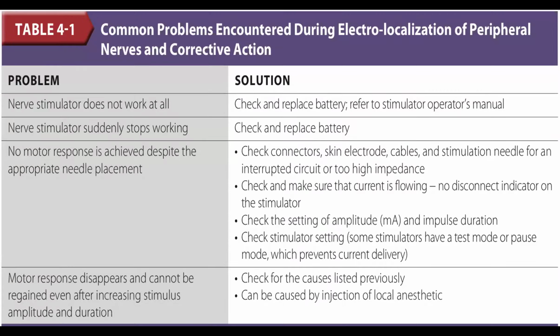And coming to common problems encountered during localization of peripheral nerves and the troubleshooting. So when the problem is that the nerve stimulator does not work at all, check and replace the battery and refer to the operator's manual. And if the nerve stimulator suddenly stops working, check and replace the battery. And if no motor response is achieved despite the appropriate needle placement, check connectors, skin electrode, cables, and stimulation needle for an interrupted circuit or too high impedance.